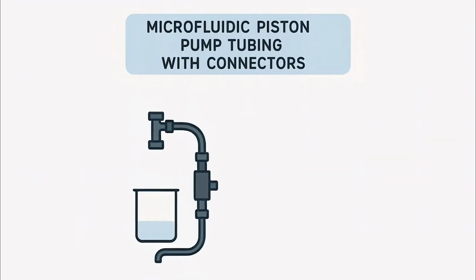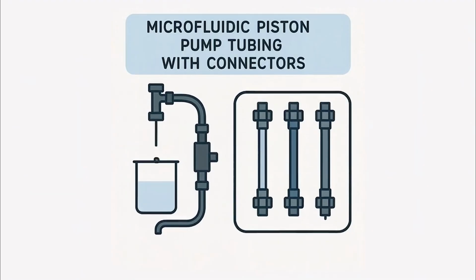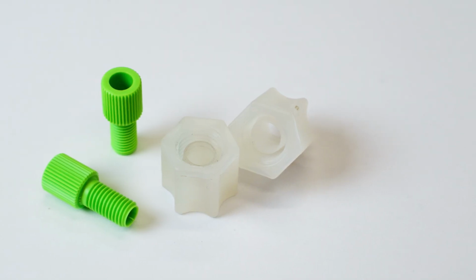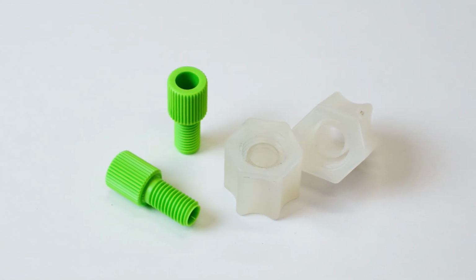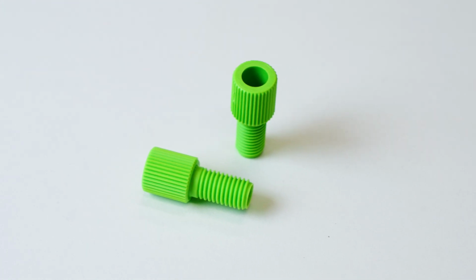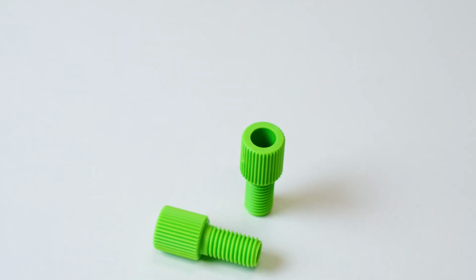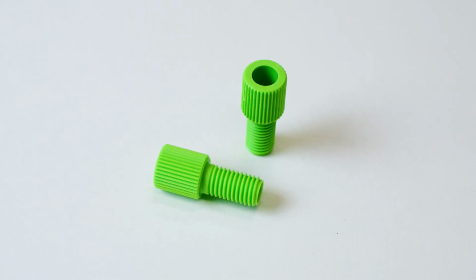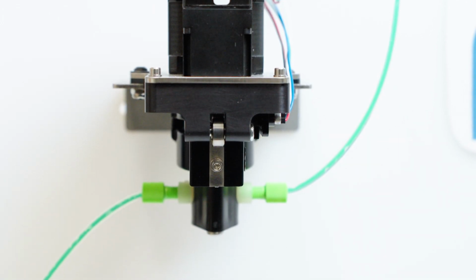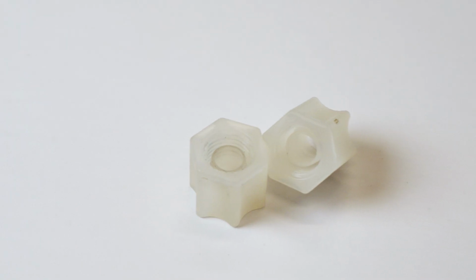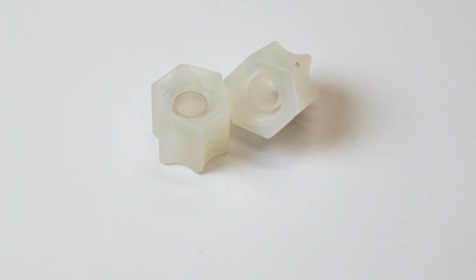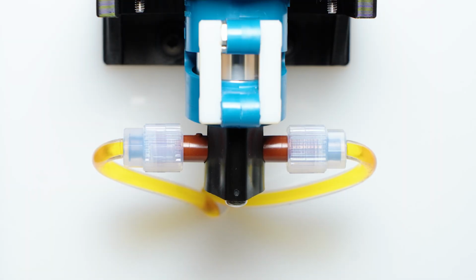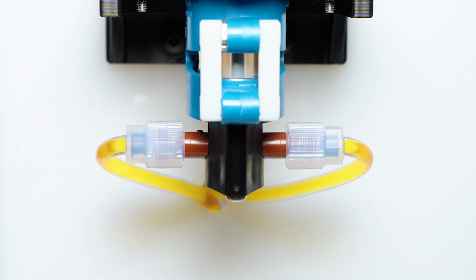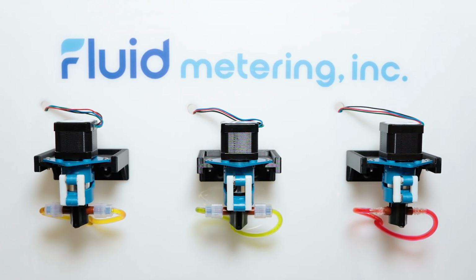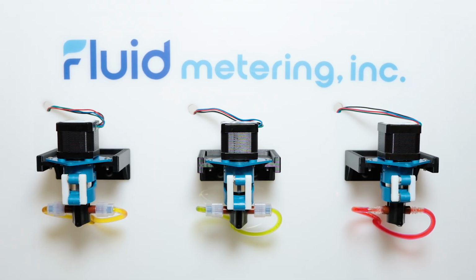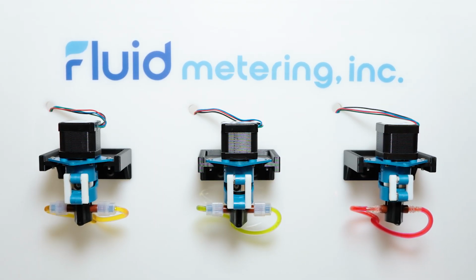Fittings should be selected according to the system flow rate and tubing interface. There are a wide variety of fittings that can be paired with our pumps. Our two most popular fitting options are quarter 28-inch UNF fittings. These are used for our low-flow applications up to approximately 50 milliliters per minute, and these are compatible with our low-flow pump heads. The next option is our quarter-inch outer diameter fittings. These are recommended for flow rates exceeding 50 milliliters per minute and are generally paired with quarter-inch tubing. Adapters are available to accommodate alternative tubing dimensions or configurations. Knowing your flow requirements is needed to select both the correct pump and fittings.